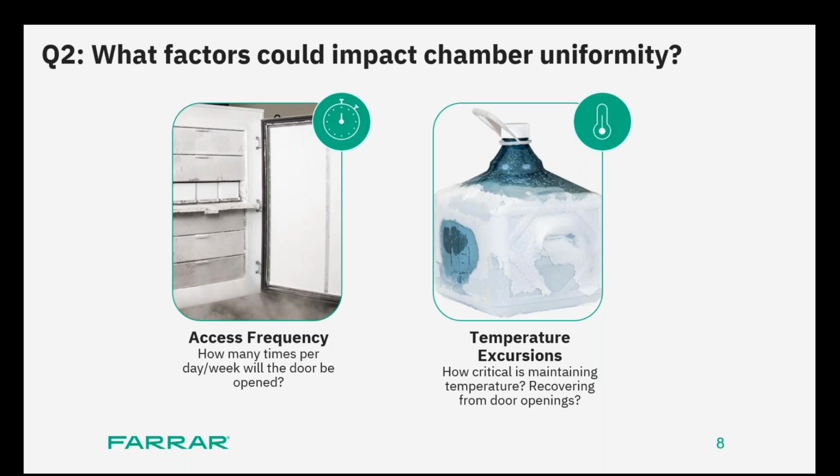So you can actually think about it and say, well, for the next 6 to 7 years, these samples would be properly and safely nestled in a -80-degree C chamber, and we don't have to really open the door. So that scenario would correlate to long-term storage with low frequency of door openings, right? And you're minimizing temperature excursion.